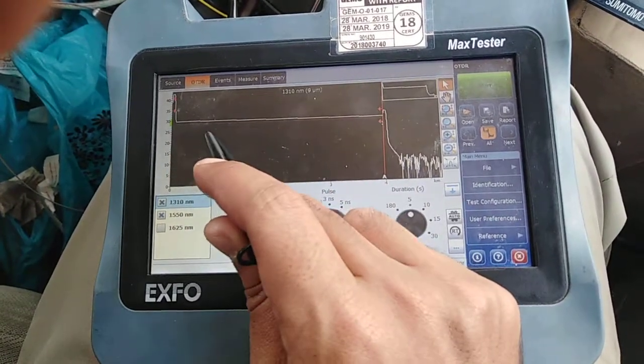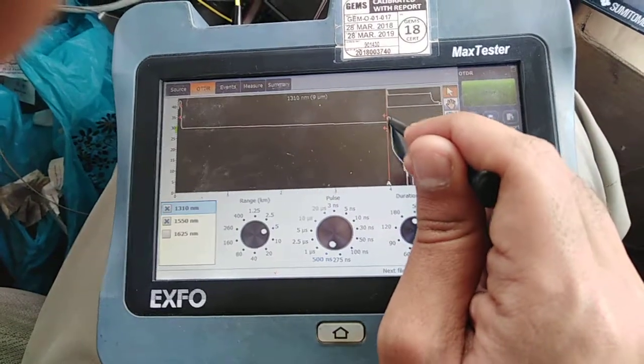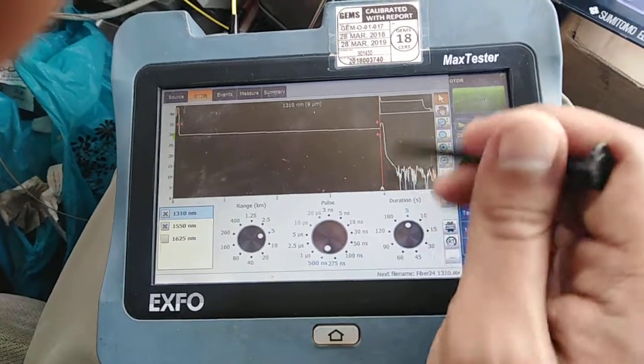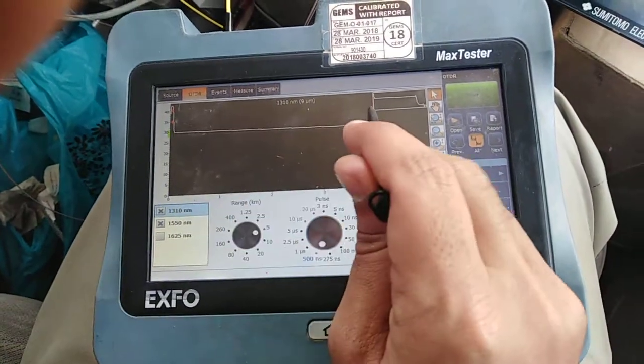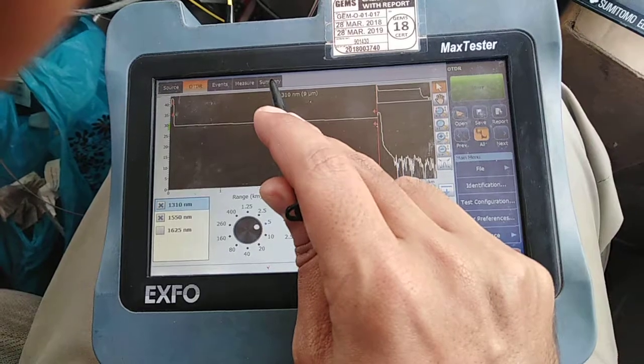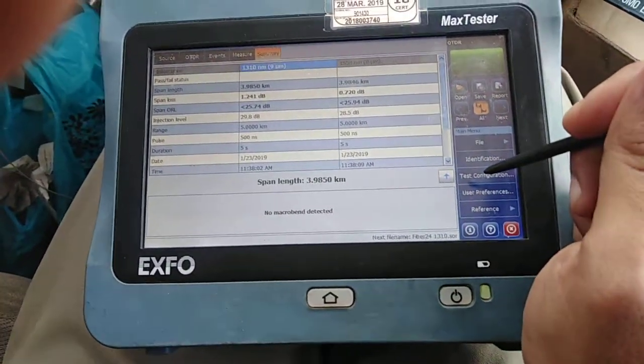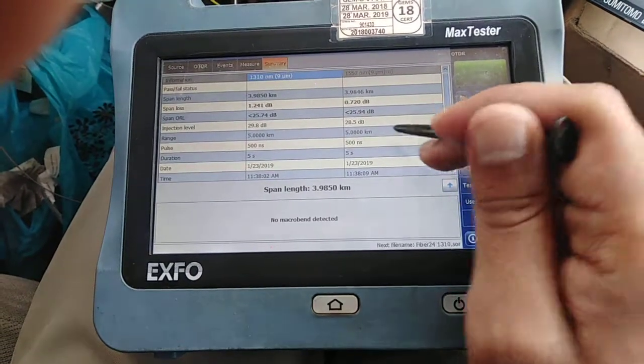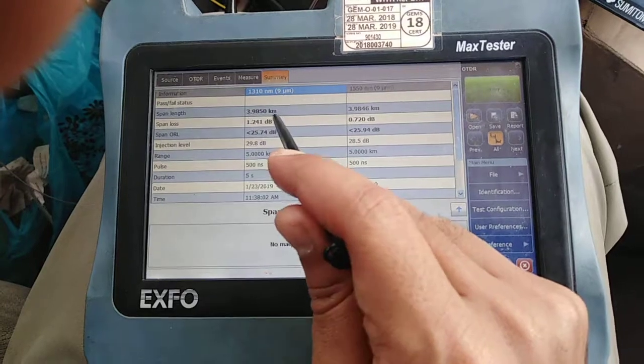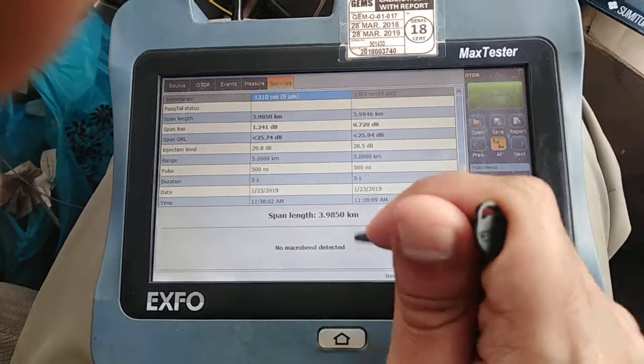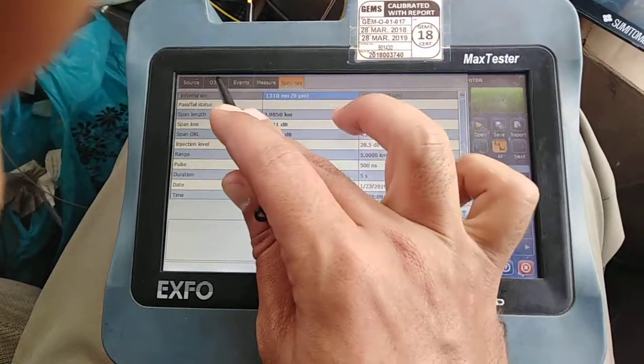Analysis is in progress again. We will go to summary. The graph is showing the fiber as straight, which means the fiber is okay. At the end it goes a little bit up, meaning at the other end there is no termination. The total length is shown in the summary for this second fiber.